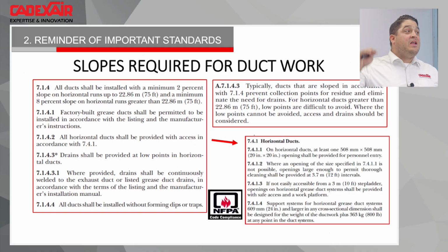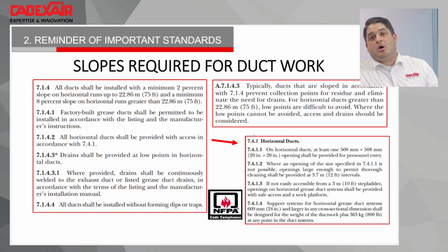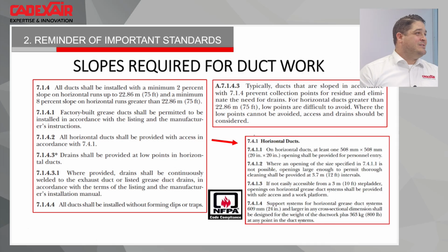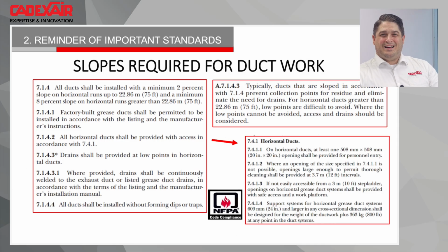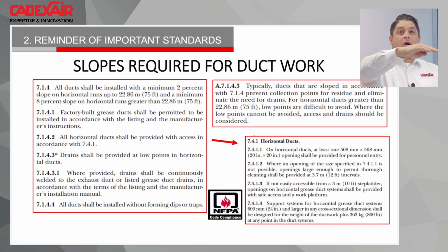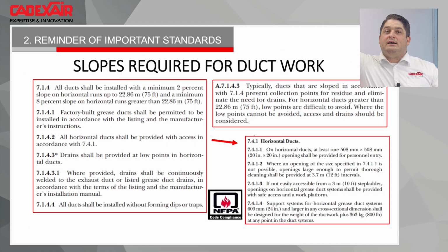You will lose 8 feet in the ceiling, so it's almost like a full residential story. 8 feet is what normal ceilings are in a house, so that's a lot. What I've been seeing on the market, and I will say it's always the authority having jurisdiction, and not a lot of them will tell you what to do. But technically, we use 2% ductwork and do zigzag like this. So what happened? You will create a low point.